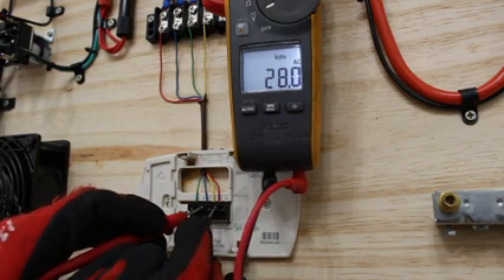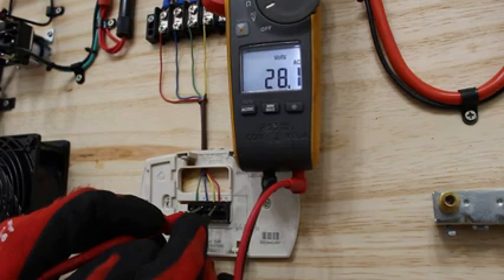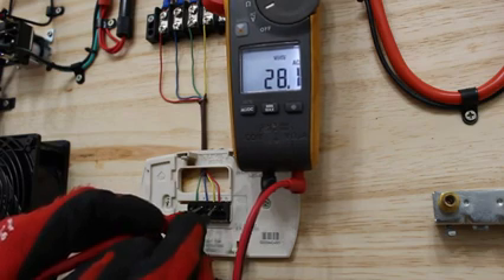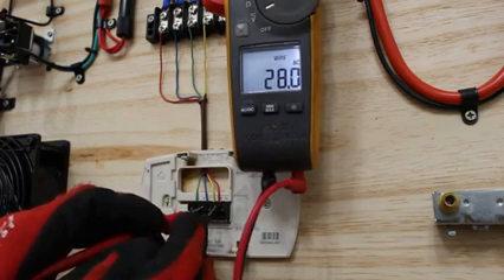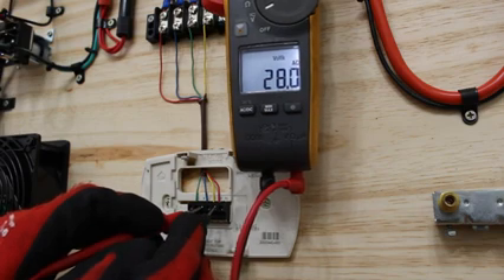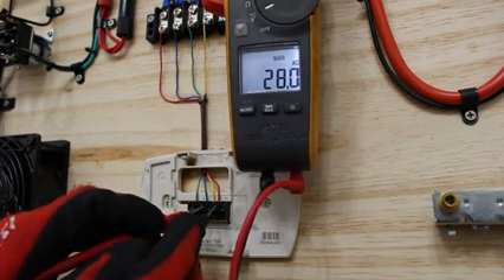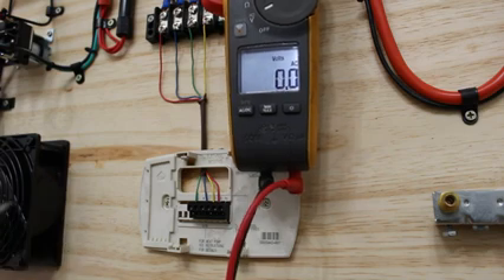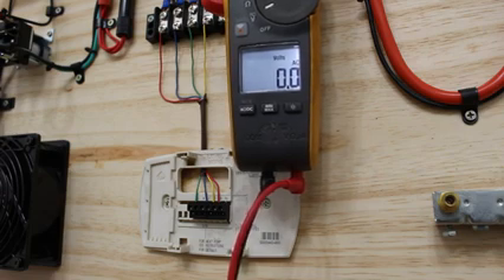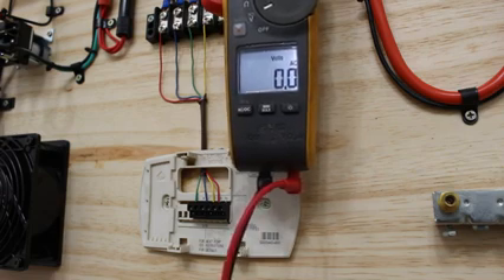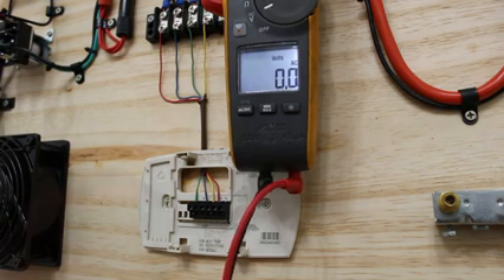Right there, we have 28 volts. There's no such thing as a perfect world. You're going to have a voltage close to 24 volts. This indicates that our transformer is good because we have our secondary voltage. The reason I go with this first is because if we have our secondary voltage, then we know we have the proper voltage on our primary and we have incoming power, and this saves the most time. In this case, our transformer is good.